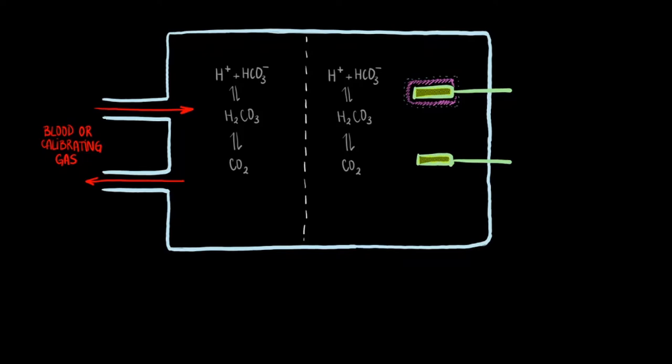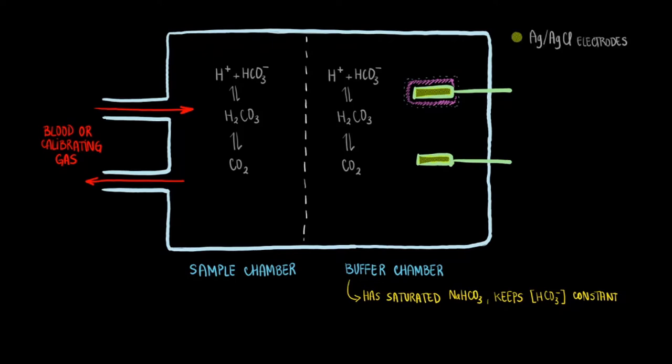The chamber on the left is a sample chamber, while the chamber on the right is the buffer chamber. The buffer chamber is saturated with sodium bicarbonate to keep the concentration of bicarbonate ion constant in the buffer chamber. In the buffer chamber, you can also see two silver/silver chloride electrodes. These electrodes are part of the standard pH electrode embedded in the Severinghaus electrode. So a voltage will be measured between the two electrodes, and this will allow the partial pressure of carbon dioxide to be calculated from a pH or voltage measurement.